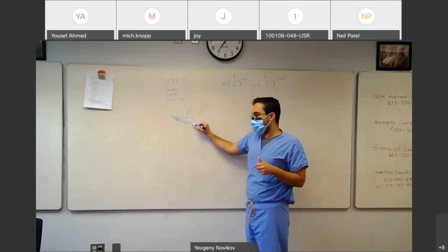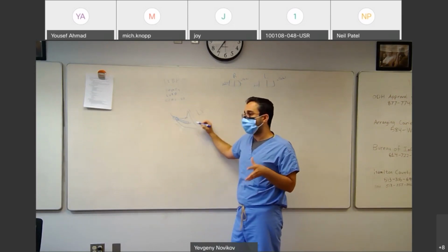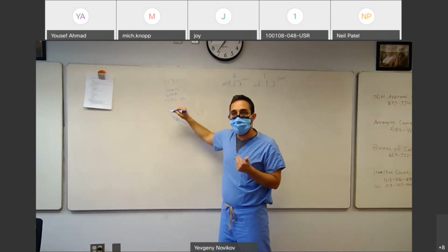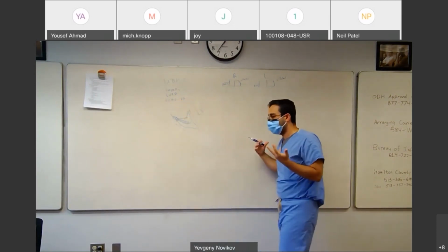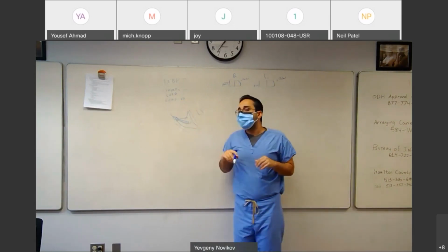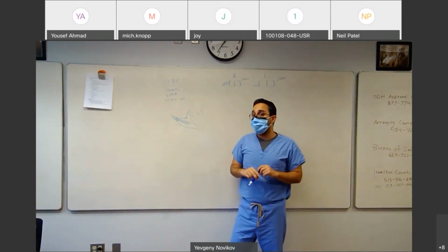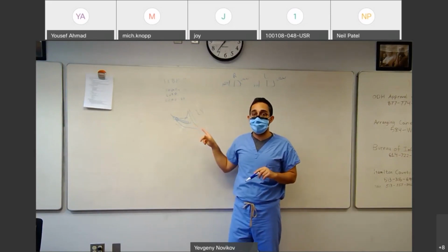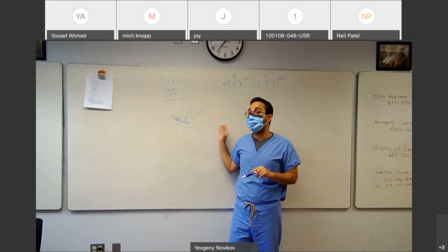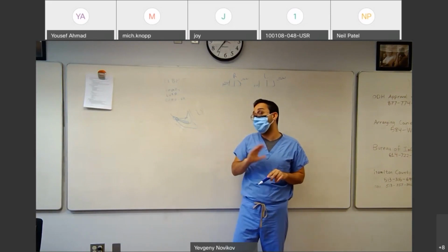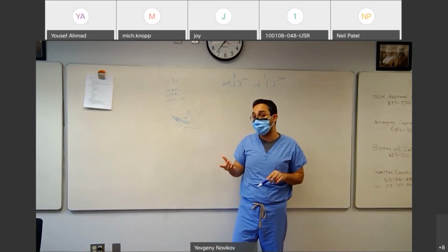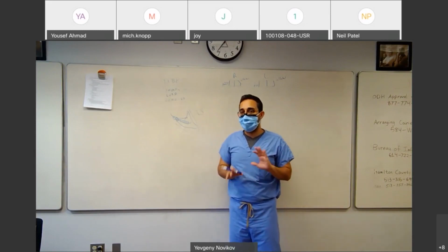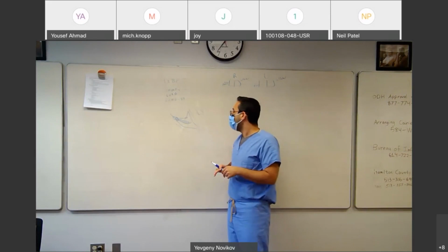It sits in kind of like mid-cavity. It sucks blood from your LV and shoots it out into your, basically, aorta, right? Now, as you can imagine, if that's pushed in too deep, it's going to be sitting in the LV. What happens if you suck from the LV and push into the LV? Not only are you not doing anything, but you're lysing the blood. So it's really good if you want hemolysis. Not really good if you're actually trying to get something meaningful out of this device.